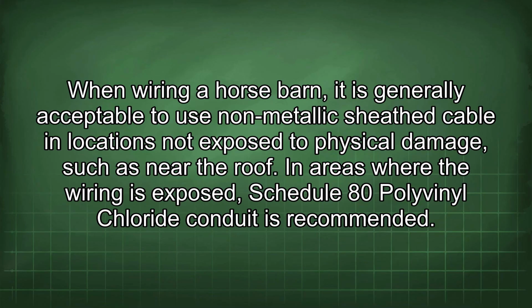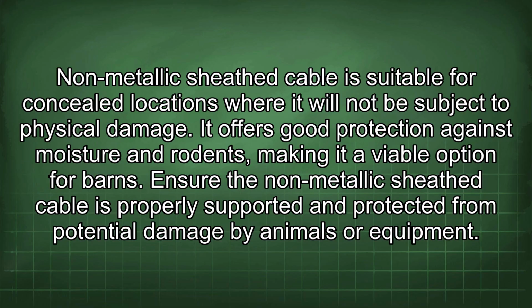When wiring a horse barn, it is generally acceptable to use non-metallic sheath cable in locations not exposed to physical damage, such as near the roof. In areas where the wiring is exposed, Schedule 80 polyvinyl chloride conduit is recommended. Non-metallic sheath cable is suitable for concealed locations where it will not be subject to physical damage.